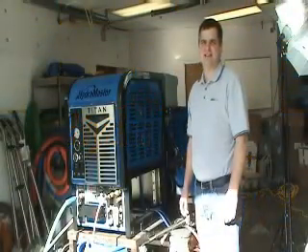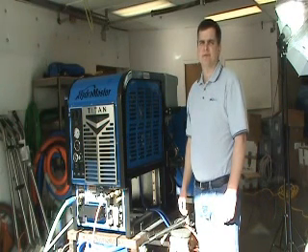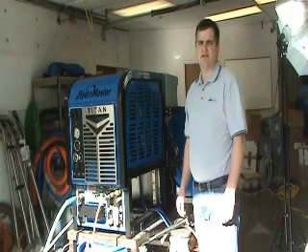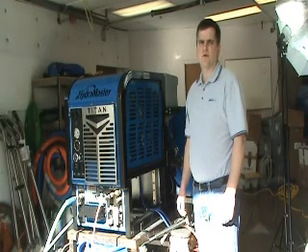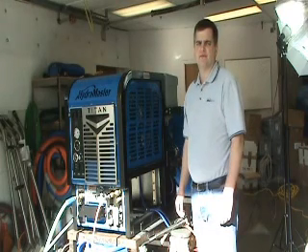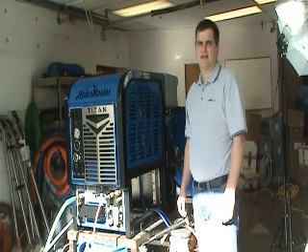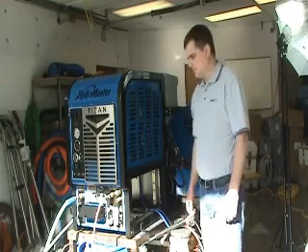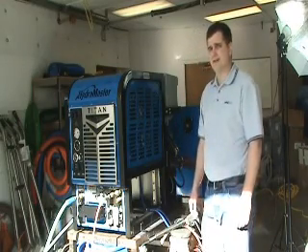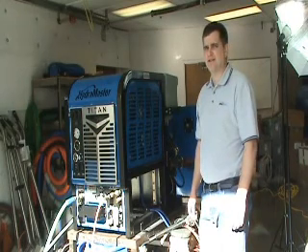In this segment, we'll discuss how to properly descale a Titan 575. Throughout the country, there are different areas of hard water deposits which can form scale in the machine, reducing its performance over time. To remove these deposits that form inside the heat exchangers and the solution circuit, we will ask you to put in a descaler. Descalers vary by manufacturer, and please follow the manufacturer's recommendations on the individual product that you use.